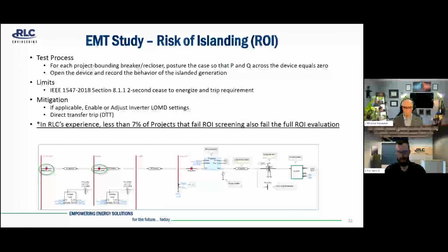So our next evaluation within the EMT study would be risk of islanding, or ROI. And this test process involves creating scenarios where real and reactive flows, or P&Q flows, are as close to 0 as realistically possible within the bounds of the actual loading on the system. So we're not going to create an unrealistic scenario, but we'll use kind of the worst case scenarios that could result in this. And we do this across any potential island. So the limits here, 1547, 2018, but section 8.1.1, their 2-second cease to energize and trip requirement, which I'm sure many of you are familiar with.